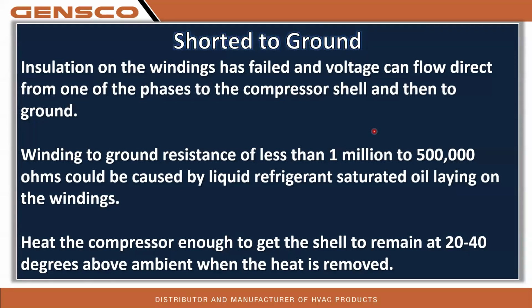If any of you guys have the maintenance tool, if it's a smart multi, the city multi maintenance tool, and if it's an M or P unit, the M&P type maintenance interface, you can look and see what the discharge temp is reading on the compressor. And I call it good to go if that discharge temp is at least 15 degrees higher than ambient air. It takes a little while for that compressor to heat up enough to get that sensor to that level. So if you see the discharge line, or you can measure it with an temp clamp, without applying your own heat to it, if it's reading at least 15 degrees above ambient, it's ready to go.